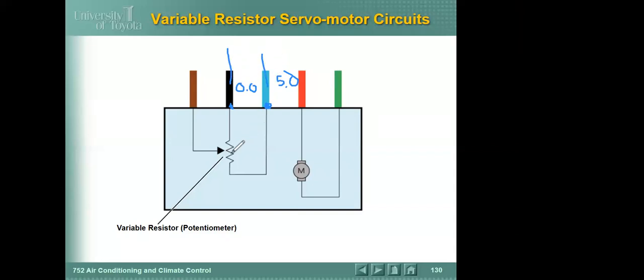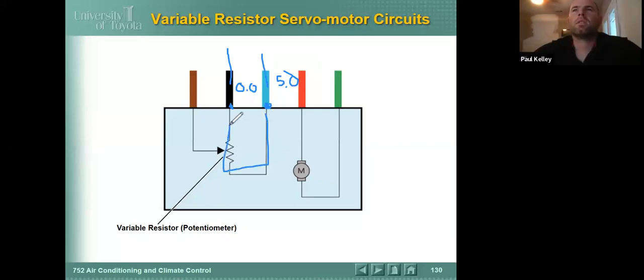It doesn't tell me anything about this or this or this. So a lot of times what we'll need to do is go to this sensor, check the 5, check the 0, and then check this one. And if this one's reading, let's say 0.0, now I'm going to trip you out—you probably won't understand this, but I'm good with it. I come in and take a jumper wire, because remember, I do the flat rate mechanic style. I take my jumper wire and jump 5 volts to here.